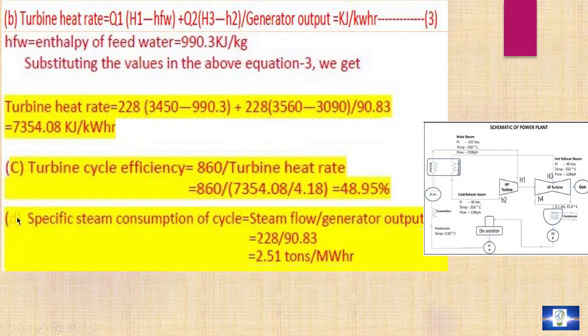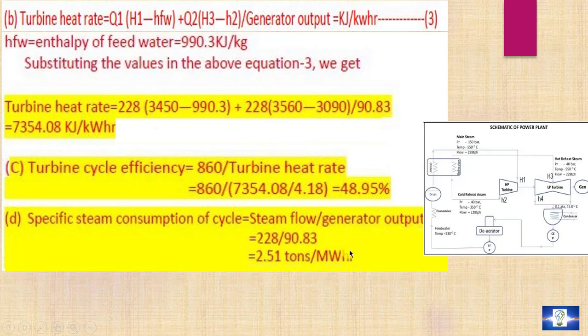The fourth question is the specific steam consumption of the cycle. Specific steam consumption equals steam flow divided by generator output: 228 ton/hr ÷ 90.83 MW. The specific steam consumption of the cycle is 2.51 ton per MWh.